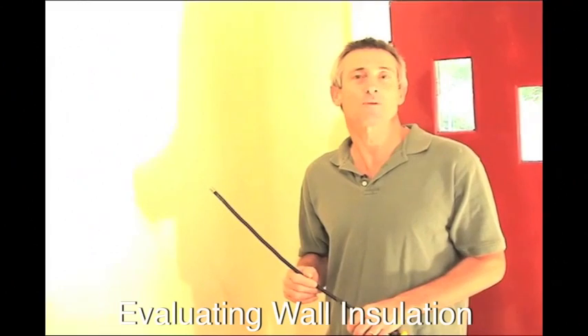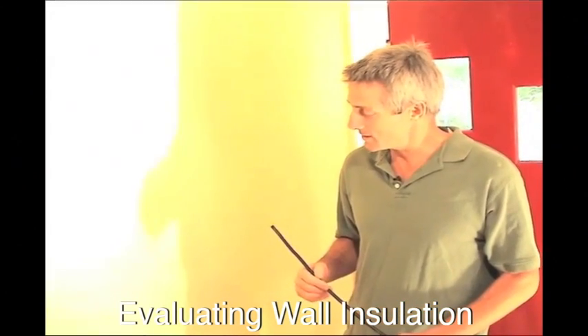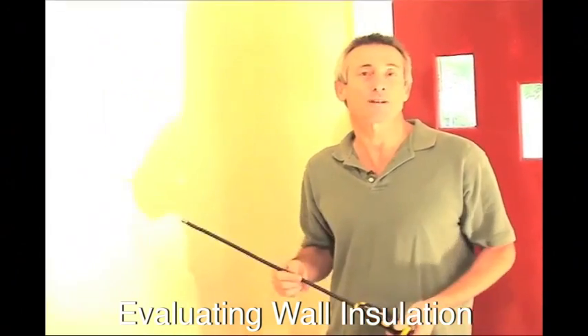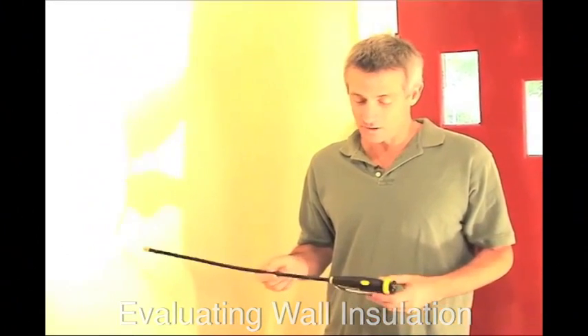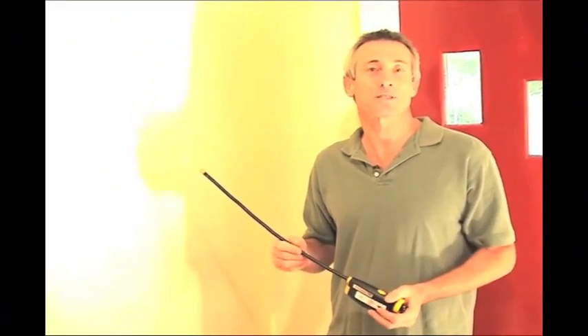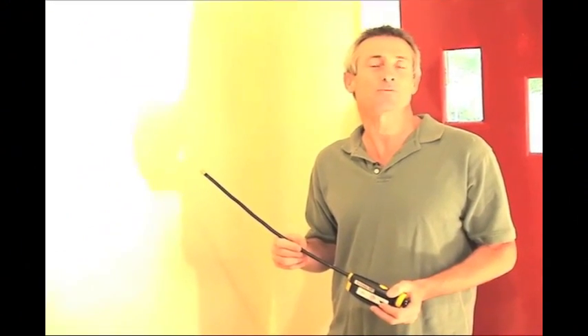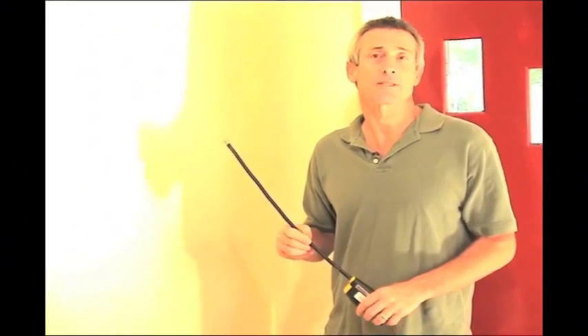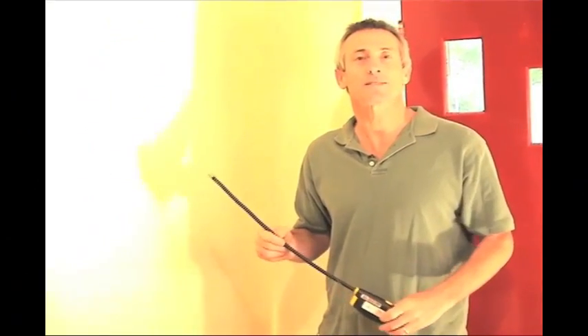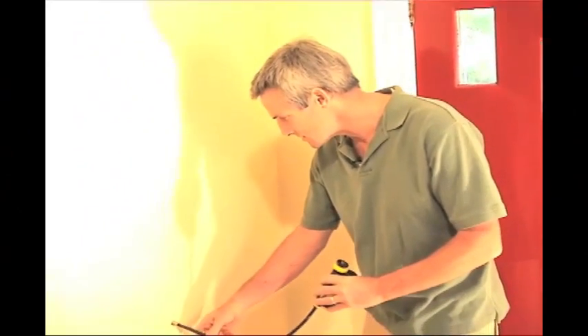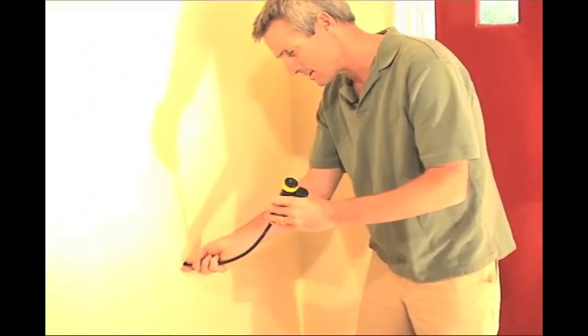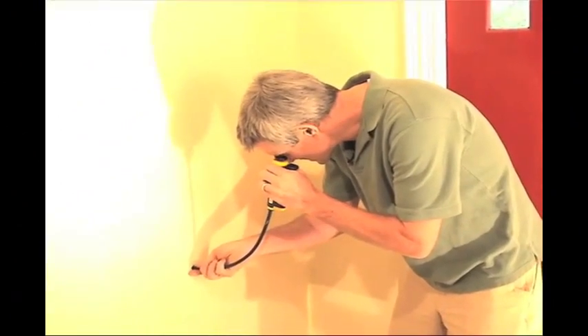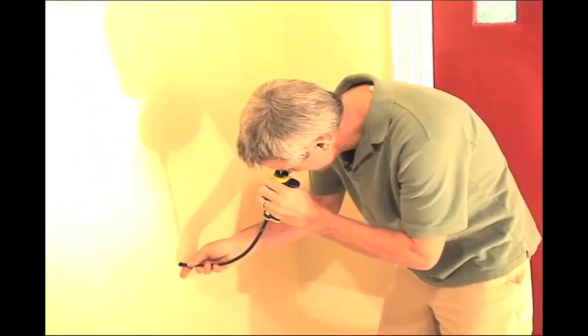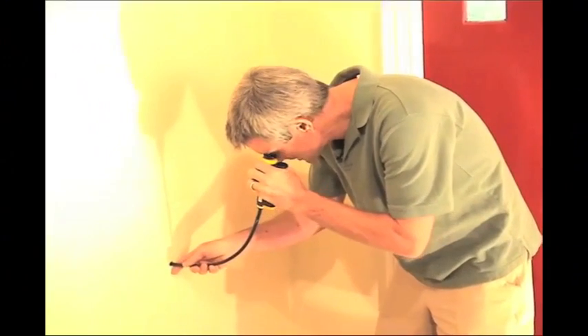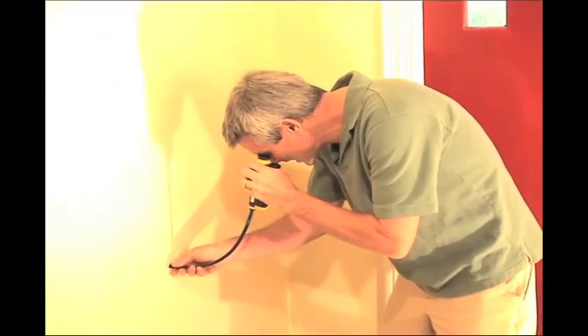We've identified just one type of wall section, and here I found an existing hole in the house. Actually, it was damaged here, where I can use this borescope to look inside and assess the insulation level. This is a great tool. They're worth $100 to $400 for different versions of this tool, but it lets you look inside cavities without having to make too big a hole. I'm going to look through this hole and determine what kind of insulation is in here, but I'll also do the same thing in 2 or 3 other places throughout the house. The tip of the probe is lighted, and I can get a surprisingly good view of what I suspect is in there, which is about a 4-inch cavity full of loose-fill cellulose insulation.